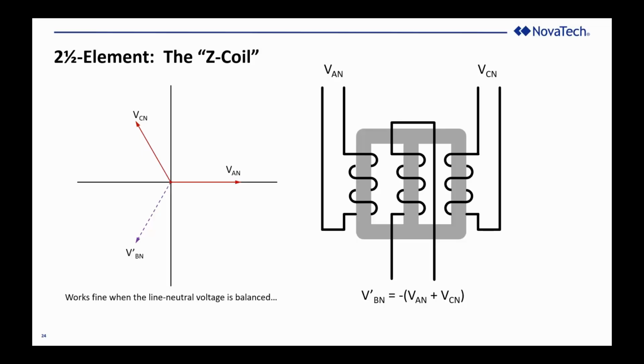And because of the shape of the core, there's a transformer inside the 2.5 element wattmeter that produces a voltage that is proportional to the vector sum of the A to neutral plus the C to neutral. It inverts the polarity, and that results in, let's call it, a synthesized B to neutral voltage. All right, that begs the question: how safe is it to assume that the A to neutral voltage plus the C to neutral voltage will produce a vector that, when inverted, is exactly equal to the B to neutral voltage?